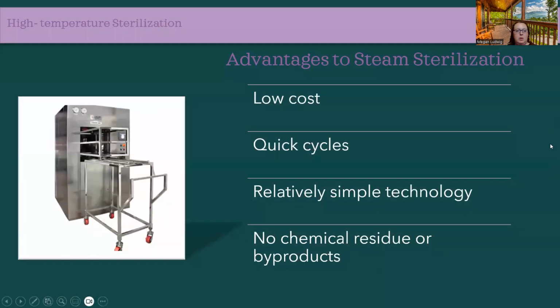Okay, so let's specifically talk about those steam sterilizers. They are low cost. They're very efficient, simple technology, so that's really why they're probably most commonly used. They're great for departments if they're low cost and simple, right? The cycles to run a load are relatively quick, and it doesn't have any harmful chemicals. Some of these others we're going to talk about have harmful, toxic, even carcinogenic chemicals used on the instruments that could be harmful to you if you become exposed to those.